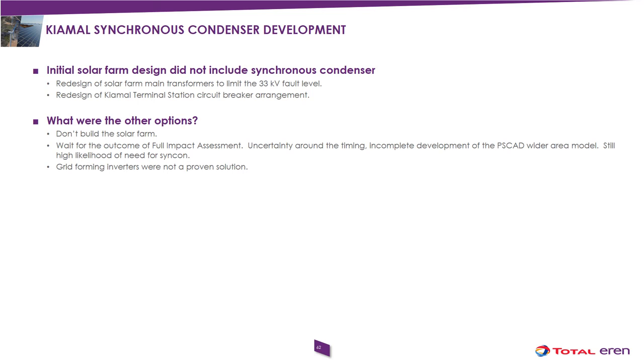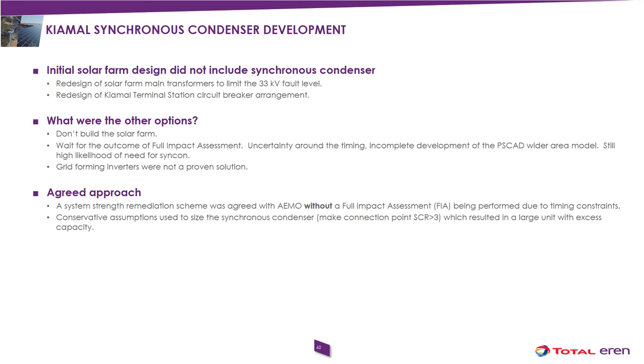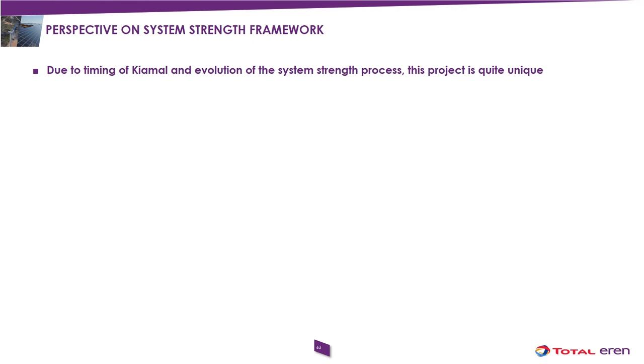With this, there was still a high likelihood for the need for a Syncon, but there was a lot of uncertainty around the time this would take, and also the PSCAD wider area model needed to perform the studies was incomplete at the time. So a system strength remediation scheme, being the Syncon, was agreed with AEMO without the full impact assessment. And conservative assumptions were made to size the Syncon to make the connection point short circuit ratio greater than 3, which resulted in a large unit with excess capacity, but a high amount of confidence that the solar farm would operate stably. So now to give my perspective on the system strength framework. I think it's clear from the previous slides that Kiamal was in a bit of a unique position in terms of the evolution of the system strength framework.